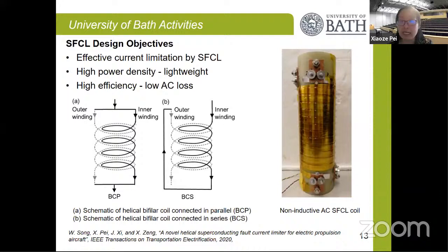Because it's a resistive superconducting fault current limiter, you normally try to reduce the inductance here. So the current goes in the opposite direction to cancel the main magnetic field, which means this is a low inductance that doesn't impact the system operation. We're looking into 2 structures: one connecting those 2 coils in parallel, which increases the current value, and another connecting those 2 windings in series, to understand what the operational difference would be. As I mentioned, superconductors don't have any losses under DC conditions, so they are perfect for DC application. They do have some AC losses.